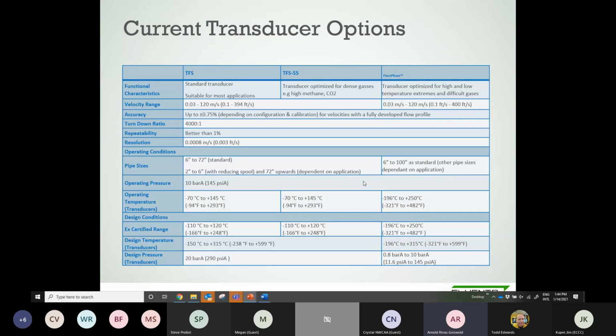The other thing is, depending on the process condition and the type of application, we can select different sensors for your application. So we have the standard transducer. It's really suitable for, I would say, 90 to 95% of the applications. This is a set of sensors that goes from 0.1 to 394 feet per second. So like I said, very wide range. This reflects basically a 4,000 to 1 turndown ratio, which is more than what you normally see in any other type of measurement. So I would say it's basically flare measurement that requires this.